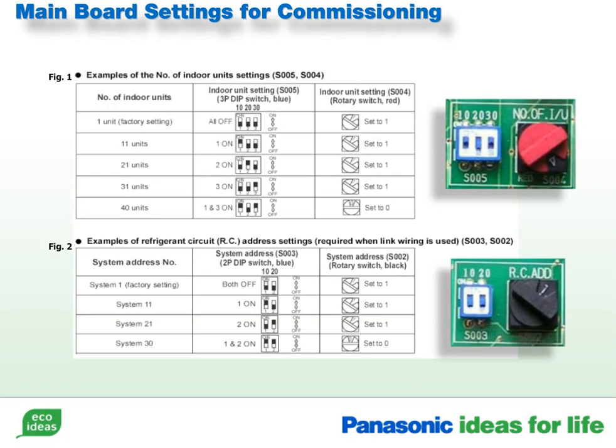Let's look at how the dip switches work with the rotary dials. In Figure 1, there are examples of the number of indoor unit settings. The factory setting of the dip switches is in the off position. In this configuration you can set up to 9 indoor units on the rotary dial.